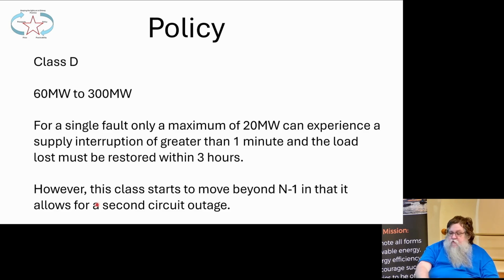And this class starts to move beyond N-1, in that it allows for a second circuit outage. So all the other ones we've talked about, if we had one fault, we would meet the standard because we got so many people back on. If we got a second fault, everything could be off if you're up to 60 megawatts of load.